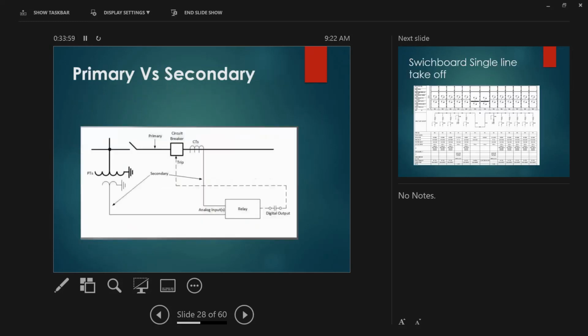Now, primary versus secondary. If you look at this simple drawing here, you have the potential transformer, which provides the voltage feed to the relay, and you have the current transformer feeding the relay, for the relay to process and monitor 24/7. If there is a normal flow of current and voltage, this one will not activate. But if there's a fault here, measured by this one, it will move and will trip the breaker. That's how simple it is.